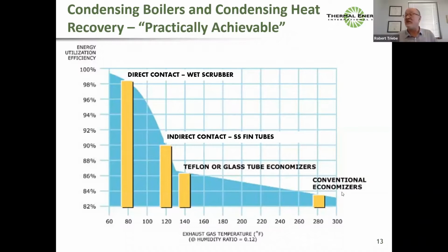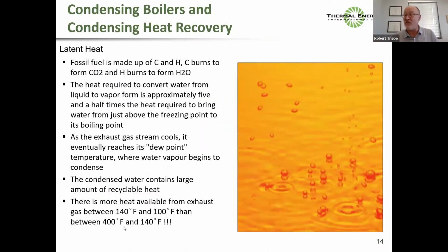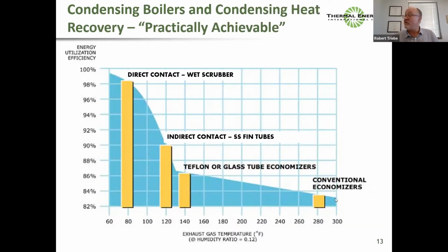As I cool, this only goes to 300. As I cool the flue gas, and I'm glad you asked because Mark, if it's not clear to you, it's not clear to everyone. As I cool this flue gas from 300, so this doesn't show 400. My statement here was from 400, which is also true. But as I cool from 300 to 140, my total efficiency improvement, I go from 83 to 86%. So I cool from 300 to 140, I get a 3% improvement. But when I cool from 140 to 100, I go from 86% to 95%. I get a 9% improvement over those 40 degrees, but I only get a 3% improvement over the previous 200 degrees. I see, okay. All right.